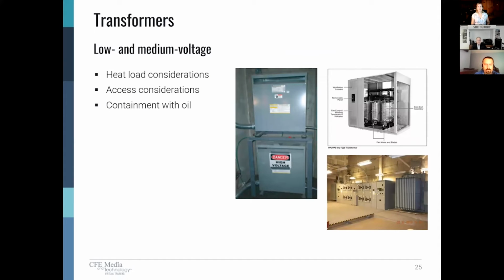So there are all types of transformers. On the left there, you see your typical dry type panel board transformer that'll be feeding receptacle branch panels and lighting panels. Sometimes these are stacked. We're often given very limited room in the design of these buildings. On the right, top right, you can see a larger dry type transformer. This is typically a medium voltage, 15 kV to 480 type transformer. And then on the lower far right, you'll see an oil type transformer, which may require containment systems.